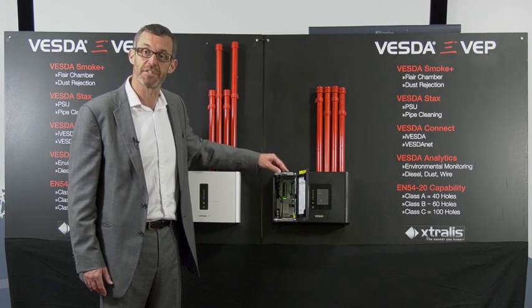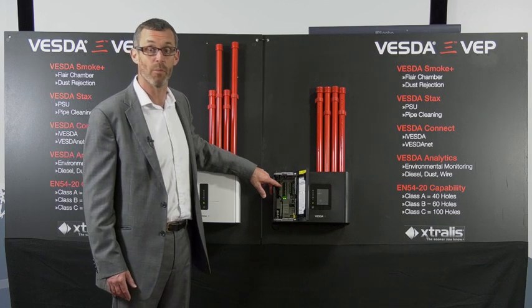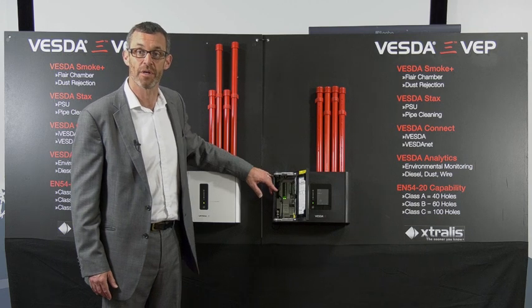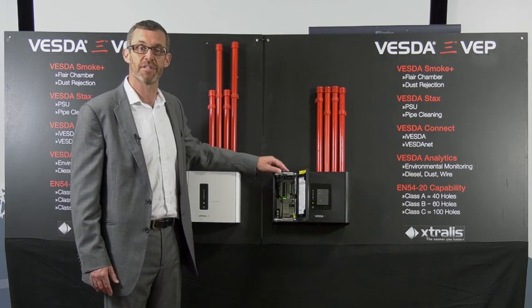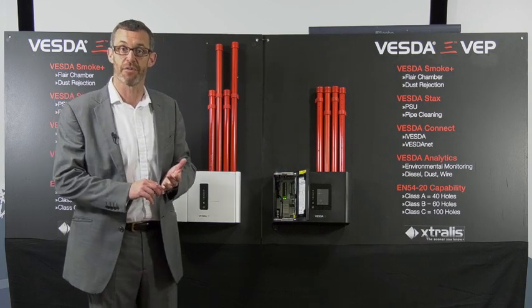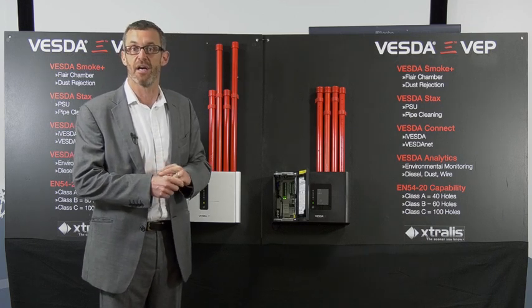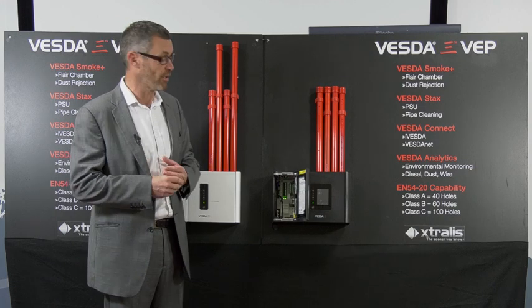Monitoring has become easier — internally there's an ethernet port so we can connect this to a LAN network, and it also has Wi-Fi so it can talk to a Wi-Fi network. This allows much easier remote monitoring. We can remotely monitor the VESDA E-range either through a PC running VSM software, or we can use iVESDA, which is an Android or Apple based connection system.